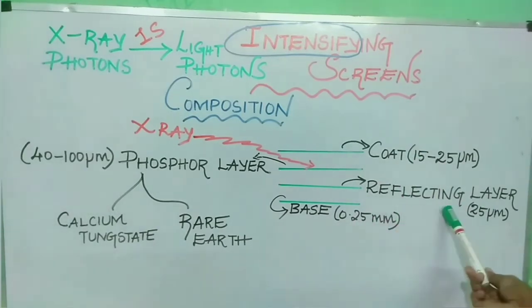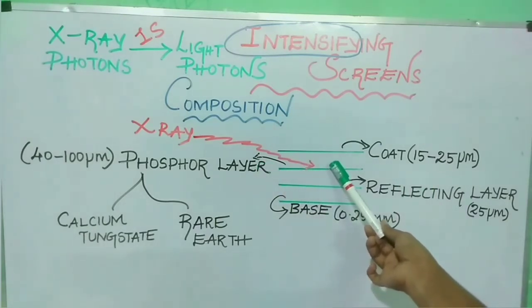Next is reflecting layer. The thickness of reflecting layer is 25 micrometers. This reflecting layer is made up of magnesium oxide or titanium dioxide. When x-ray photons interact with the active phosphor layer, light photons are emitted in all directions. The reflective layer redirects those emitted light towards the film.